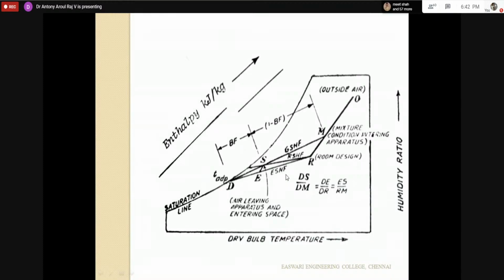What is the use of that? You can draw the effective sensible heat factor line with that slope, through R, and from there it will be going and touching the saturation line - that is the ADP line. As per room condition the ADP should be somewhere here, but I'm bringing down the ADP. How to find that ADP? By finding the effective sensible heat factor line only.